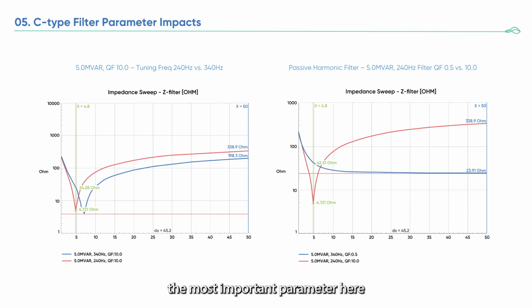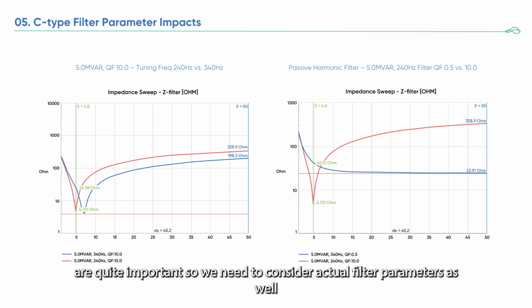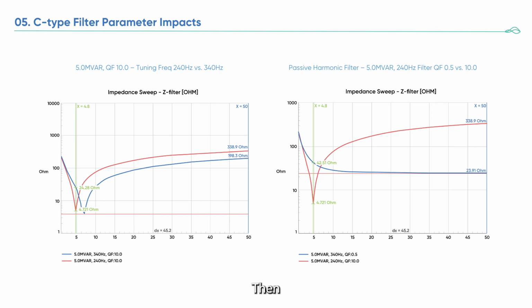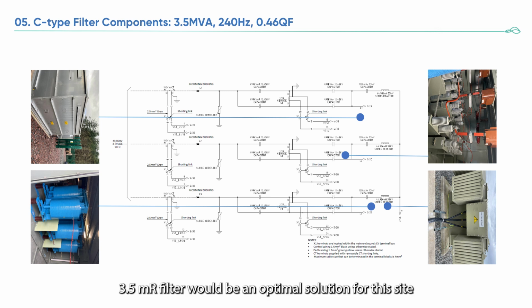And also, the most important parameter here, knowing actual filter components, is quite important. In the simulation world, we can design a very good filter. It can be very good in the model, but in the real world, it may not be possible to build that filter physically. So designing the filter considering actual filter parameters is quite important. So we need to consider actual filter parameters as well. Then we decided that a 3.5 MVAR filter will be an optimal solution for this site.